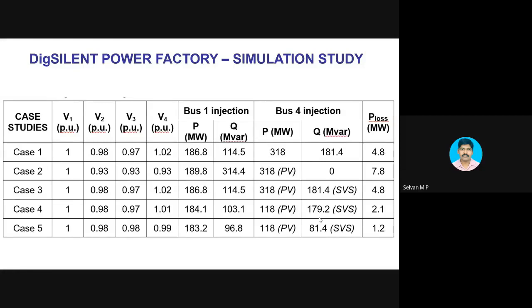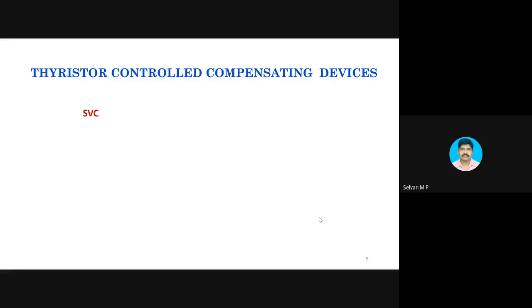So it is not a good reactive power source for critical situations when the voltages are too low. If slightly low, okay, but if too low, then we cannot use capacitor banks to improve the voltage profile to the required value. So I need a dynamically changing reactive power source. People identified many compensating devices other than the capacitor.